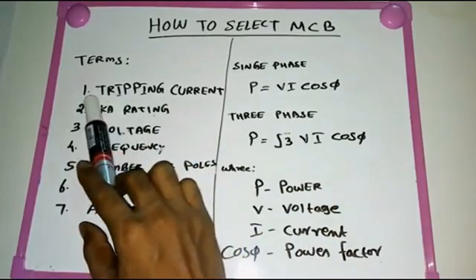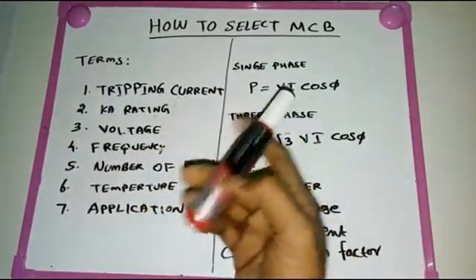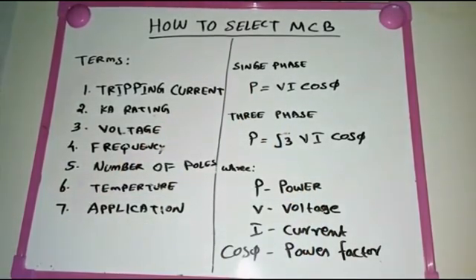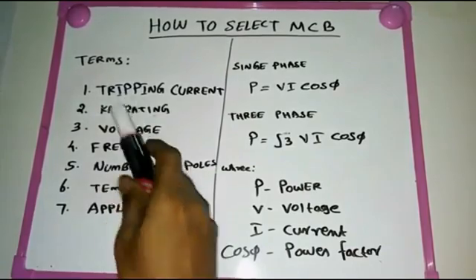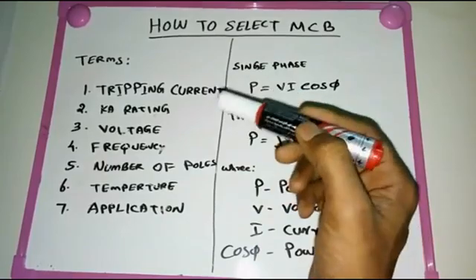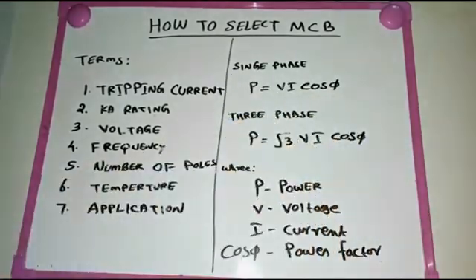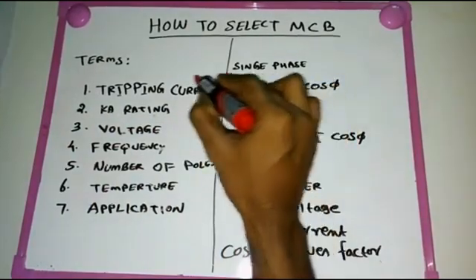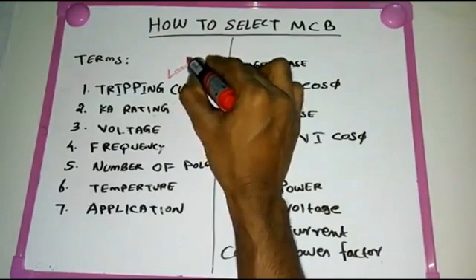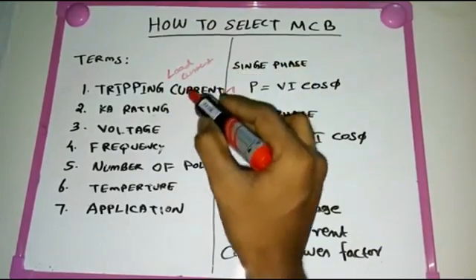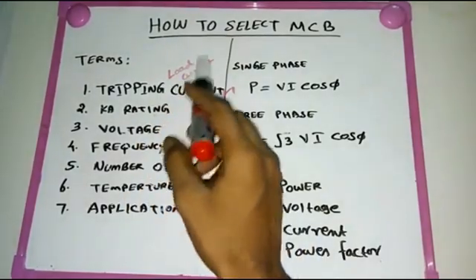The first term is tripping current. Tripping current means: when more than that current passes through the MCB, it will trip the circuit and isolate the faulty section from the healthy section. The tripping current we choose must be more than the load current. For example, if we have a load current of 8 ampere, we need to select a 10 ampere tripping current MCB.